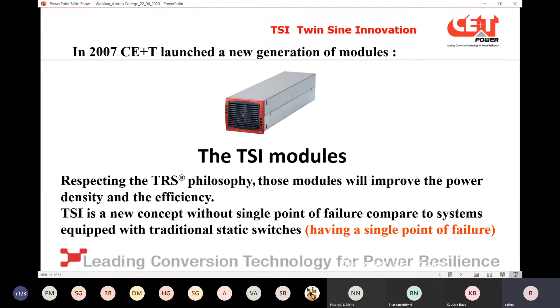We are the first company in the world to introduce a hot swappable AC backup inverter solution that is modular, called the TSI, twin sine inverter. This module is about 2.5 kVA and 2 kilowatts. It's a modular inverter, not a UPS, and this concept allows us to eradicate the single point of failure compared to traditional systems, which we'll see later.